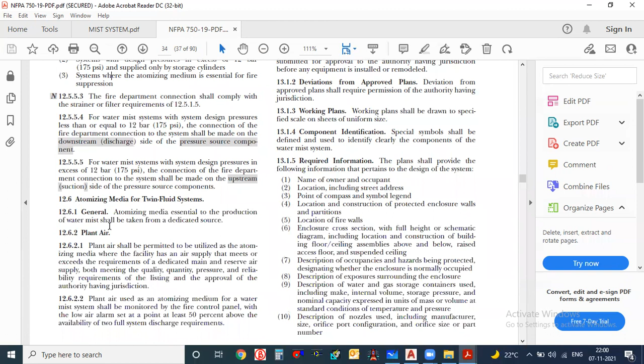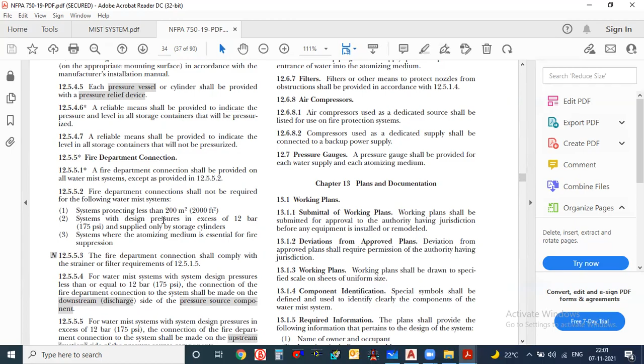If the area is less than 2000 square feet, we don't need a fire department connection. The system can still be used, but the fire department connection cannot, because once the fire department connection comes in, we have to design a hydrant system and sprinkler system too, since fire department connections typically go for hose connections.